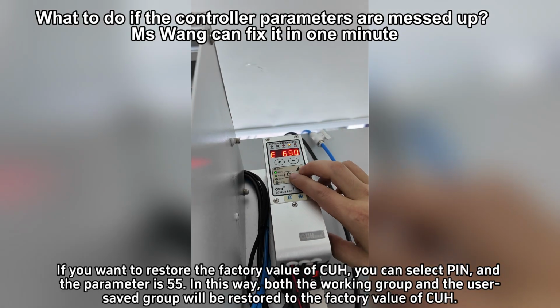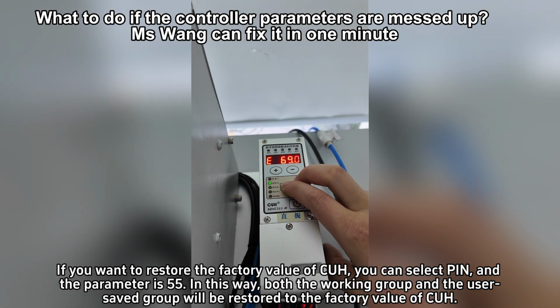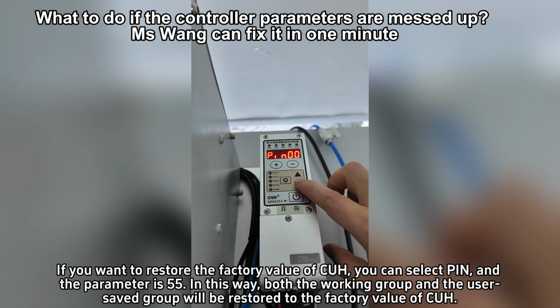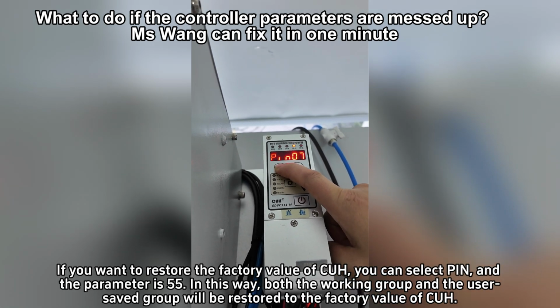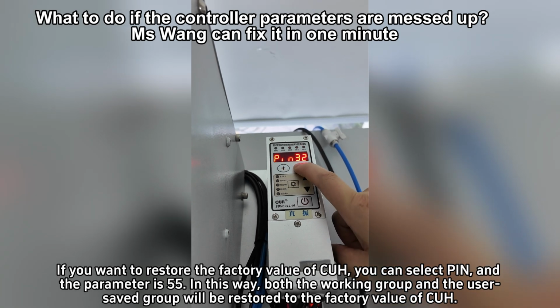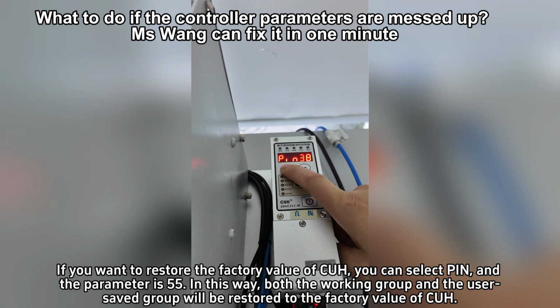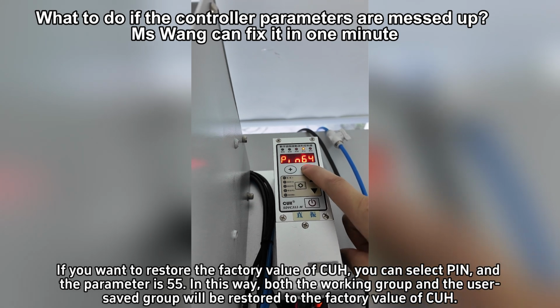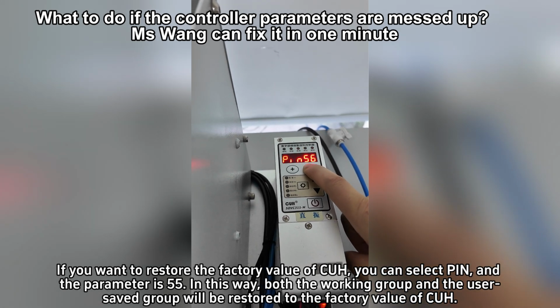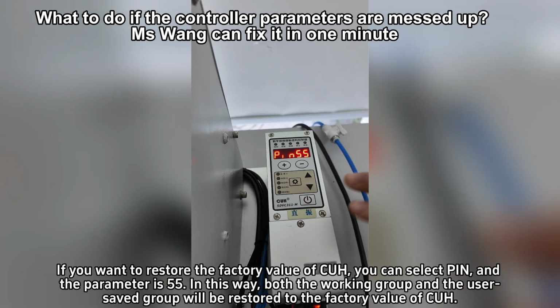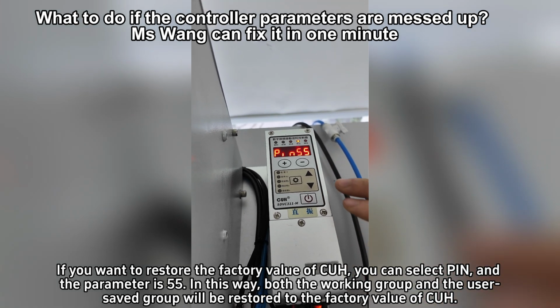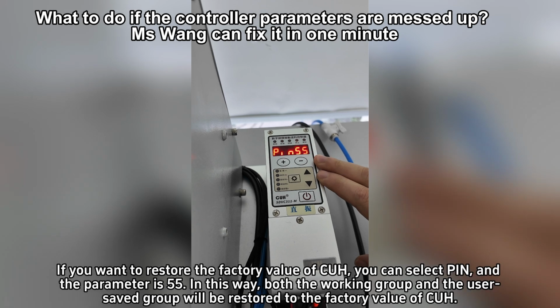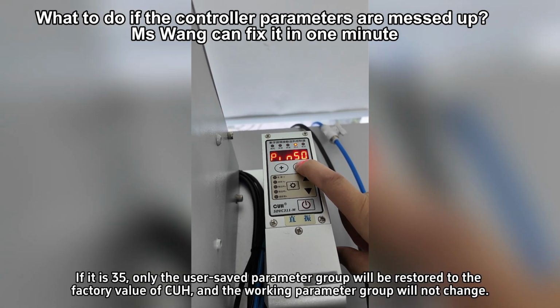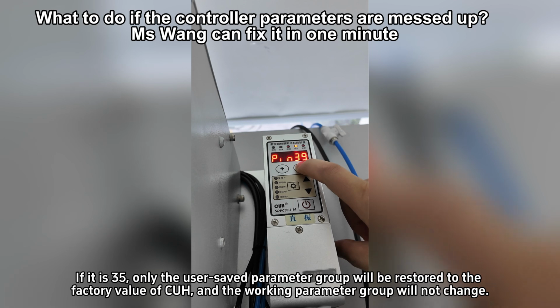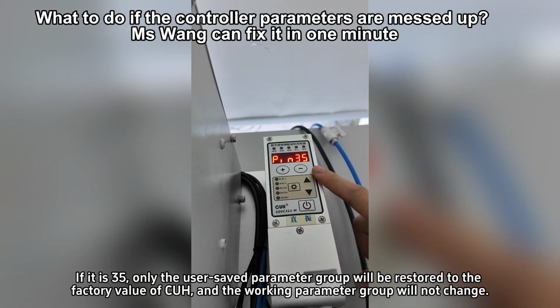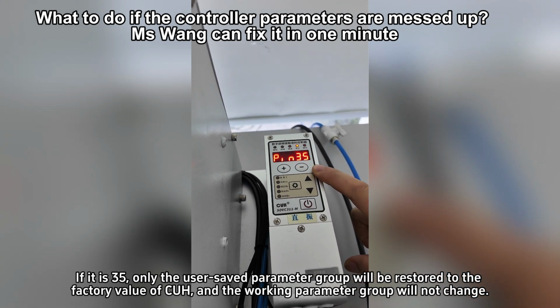If you want to restore the factory value of CUH, you can select pin, and the parameter is 55. In this way, both the working group and the user saved group will be restored to the factory value of CUH. If it is 35, only the user saved parameter group will be restored to the factory value of CUH, and the working parameter group will not change.